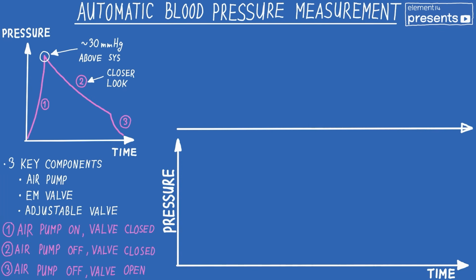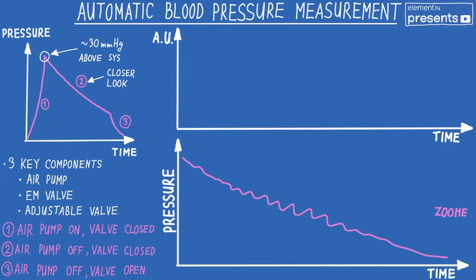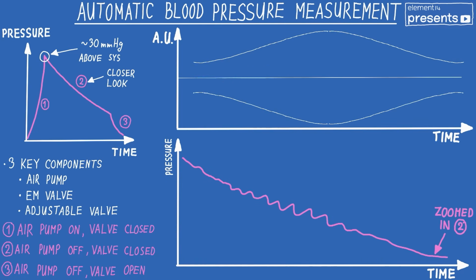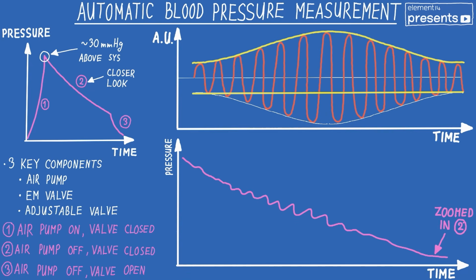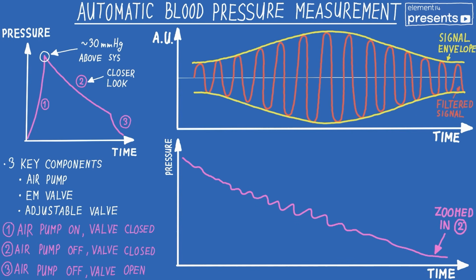Now let's take a closer look at the second segment. You can see it here. Now if we filter that signal, we can see this red line, which are the pulsations you can see in the pink line, just detrended literally, and in the yellow you can see the signal envelope. Now we want to get all of our data from that signal envelope. If we find the max value of that envelope and find the time at which the max of the envelope occurred, we can actually estimate the mean arterial pressure.